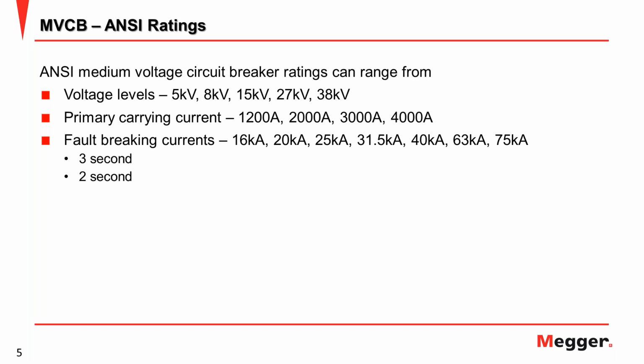And based on the fault breaking current, there are 16 kA, 20 kA, 25 kA, up to maybe 75 kA you can find in the market. The fault breaking current is the current that the breaker is able to interrupt without being destroyed or causing an electrical arc of unacceptable duration. Mostly they have a time limit, for example 3-second breaking current or 2-second breaking current.